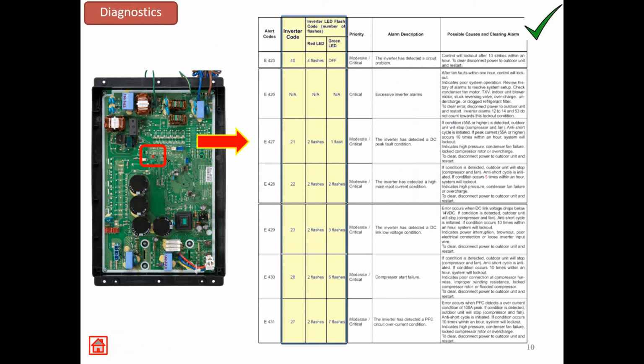So for instance, compressor start failure is a 430, and I see that from time to time. After 10 starts, it's going to go to a 434 code, and it goes into a lockout, so it doesn't start after 10 tries. This happens from time to time when we get too much refrigerant in the system, the line sets too big, things like that.